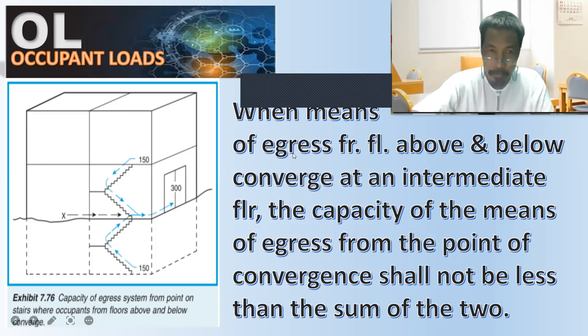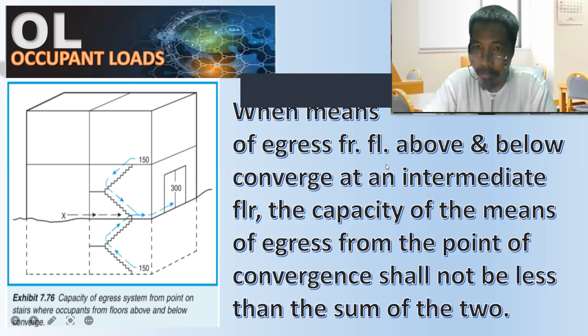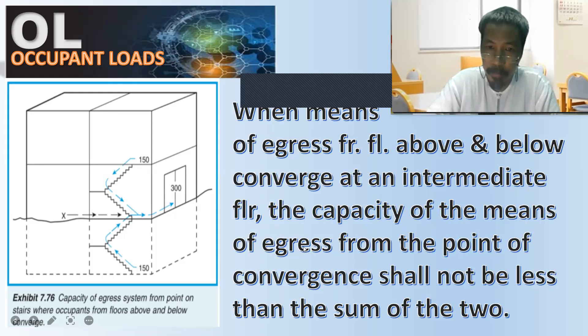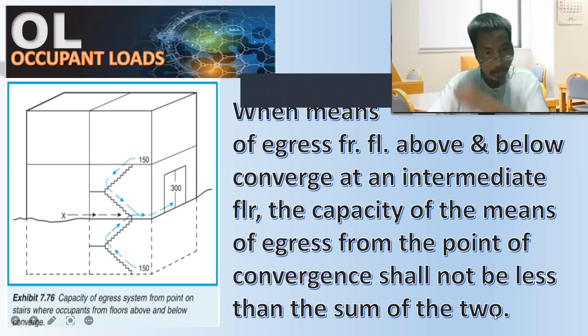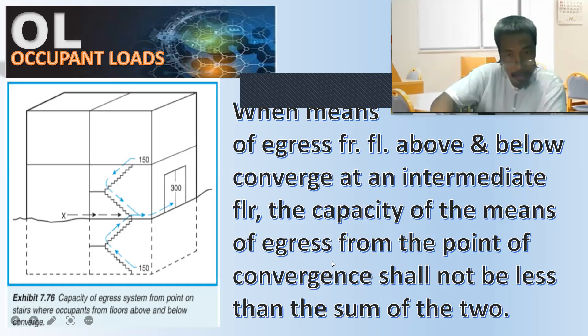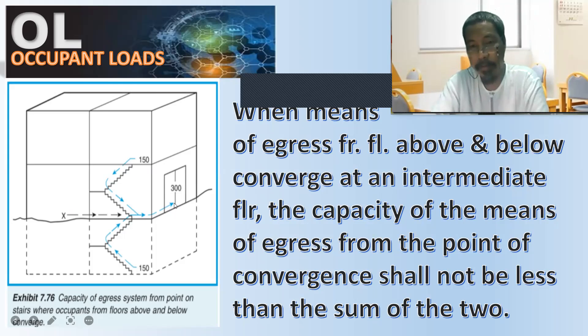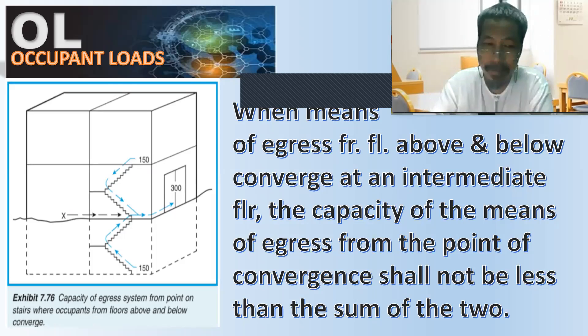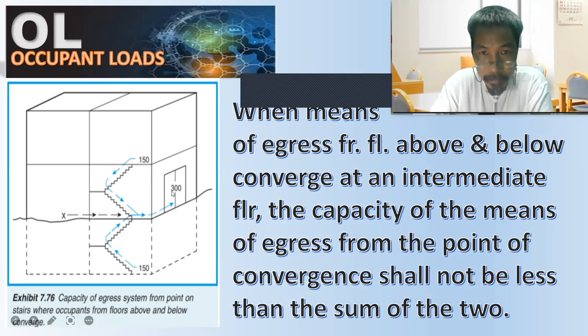When means of egress from floors above and below converge at an intermediate floor, the capacity of the means of egress from the point of convergence shall not be less than the sum of the two. So it could be equal or more, but not less. The minimum requirement is equal — it could be more, but not less — so it could be 300.